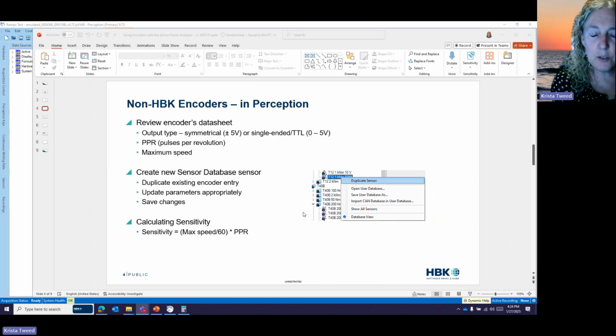All right, now this is where all the questions tend to come in. So someone contacts me and says, I have my own encoder that I want to use with eDrive. What do I do? The first thing is to pull up that encoder's data sheet. And there are three main pieces of information that you're going to need off that data sheet. You need to know what type of output that sensor puts out. Is it a symmetrical plus minus 5 volts or a single-ended 0 to 5? The symmetrical will typically have 2 pins outputting that plus minus 5, whereas the TTL, you're just going to have a single pin and the ground connection for each of those encoder signals. You need to know the pulses per revolution for the sensor, and you need to know the maximum speed that it can support.